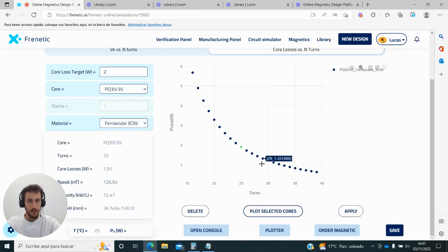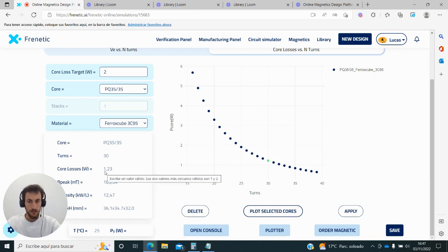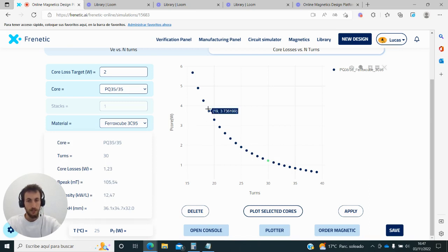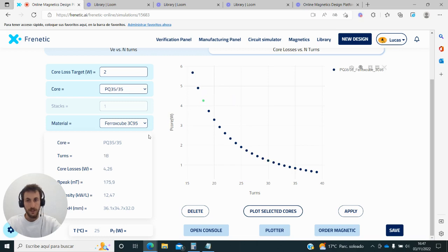If I increase the turns, obviously I reduce the flux and therefore reduce the core losses. The other way around, if I reduce the number of turns, I increase the magnetic flux in my core and increase the core losses.